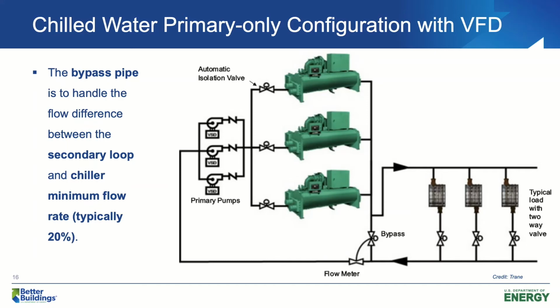It will overcome the pressure loss across the evaporators of chillers, along the pipelines, and across the coils. Then we can put VFDs on our primary pumps. This way, we can modulate the pump speed and chill water flow rate to match the cooling load. But as you know, although our chillers can have variable flow rate through evaporators, they still have a minimum flow requirement. Typically, the minimum flow requirement is about 20% of design flow rate.